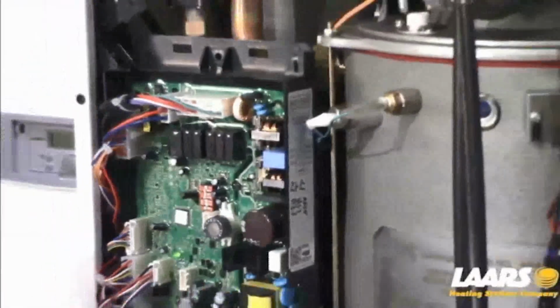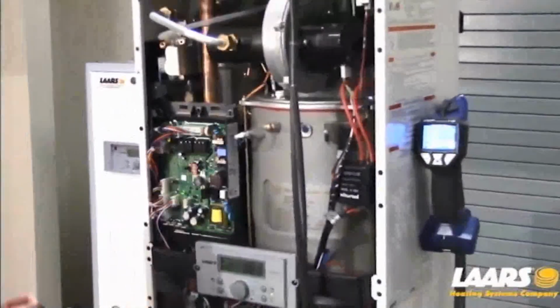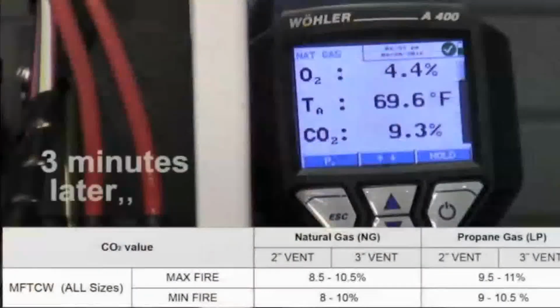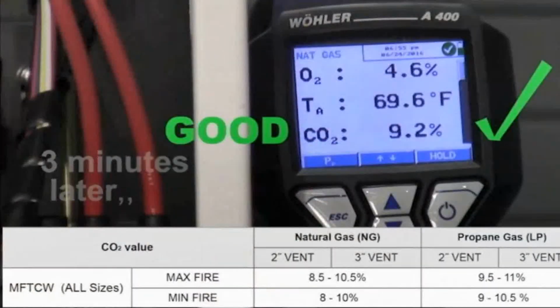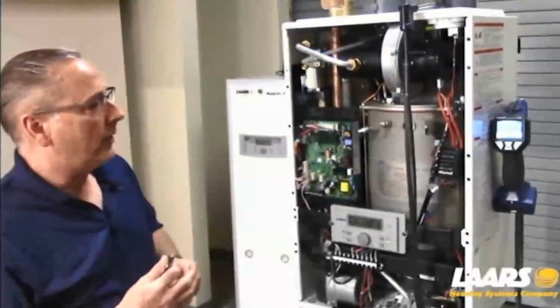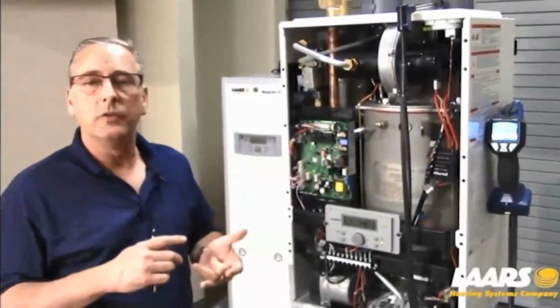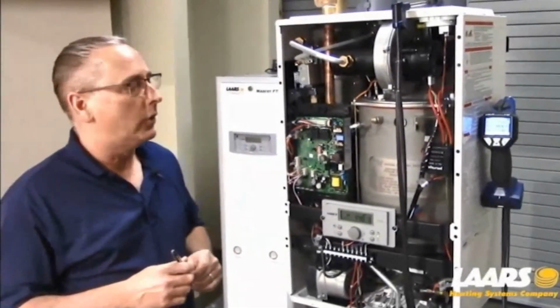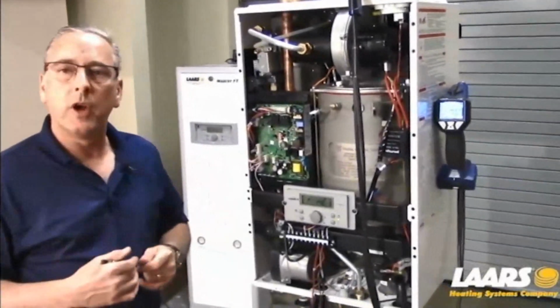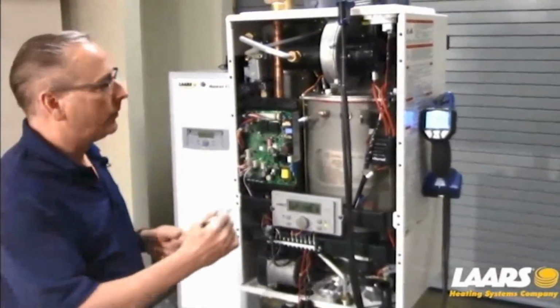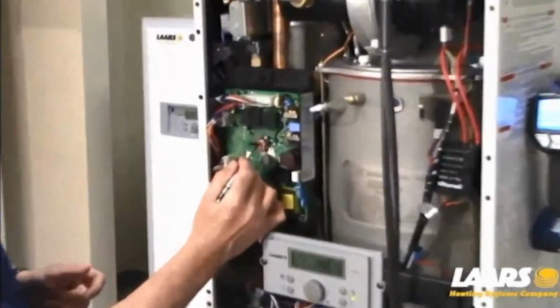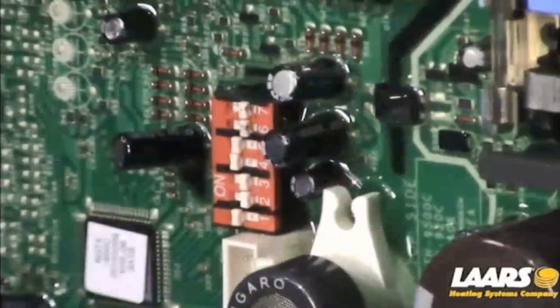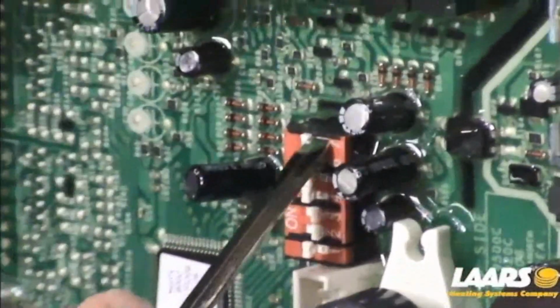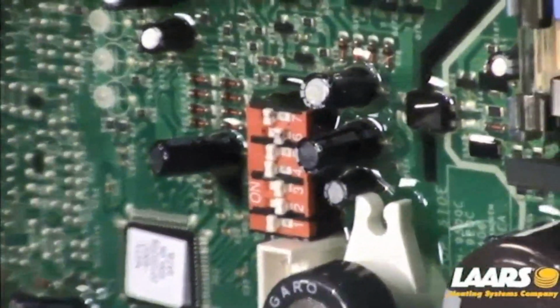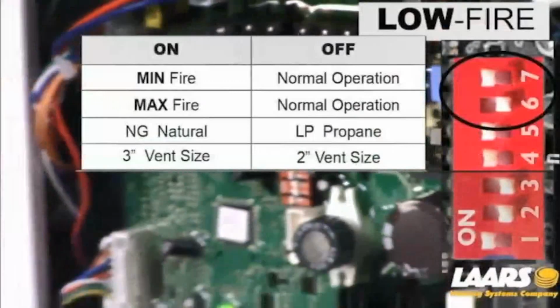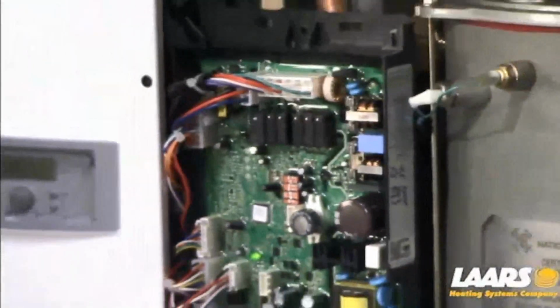Once we've run in high fire, we wait and make sure we're within range. Okay, so now that we've checked our high fire, we're running around 9.2, 9.3% CO2. We'll go back in one more time and double check our low fire. I'm going to throw dip switch 6 to the right-hand position, dip switch 7 to the left-hand position. Be patient with your analyzer. Let that modulate down and double check your low fire adjustment.